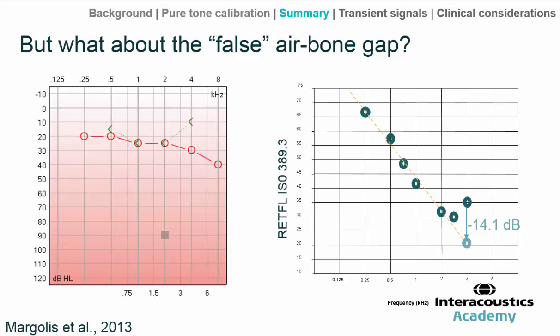If this 14.1 dB is subtracted from the reference equivalent threshold force level, it falls much closer to the line of best fit, or the extrapolated line of best fit. So it seems as though there's an error in the reference equivalent threshold force level. They didn't check 3 kHz as they didn't have enough data, but it's probably the case at 3 kHz too.